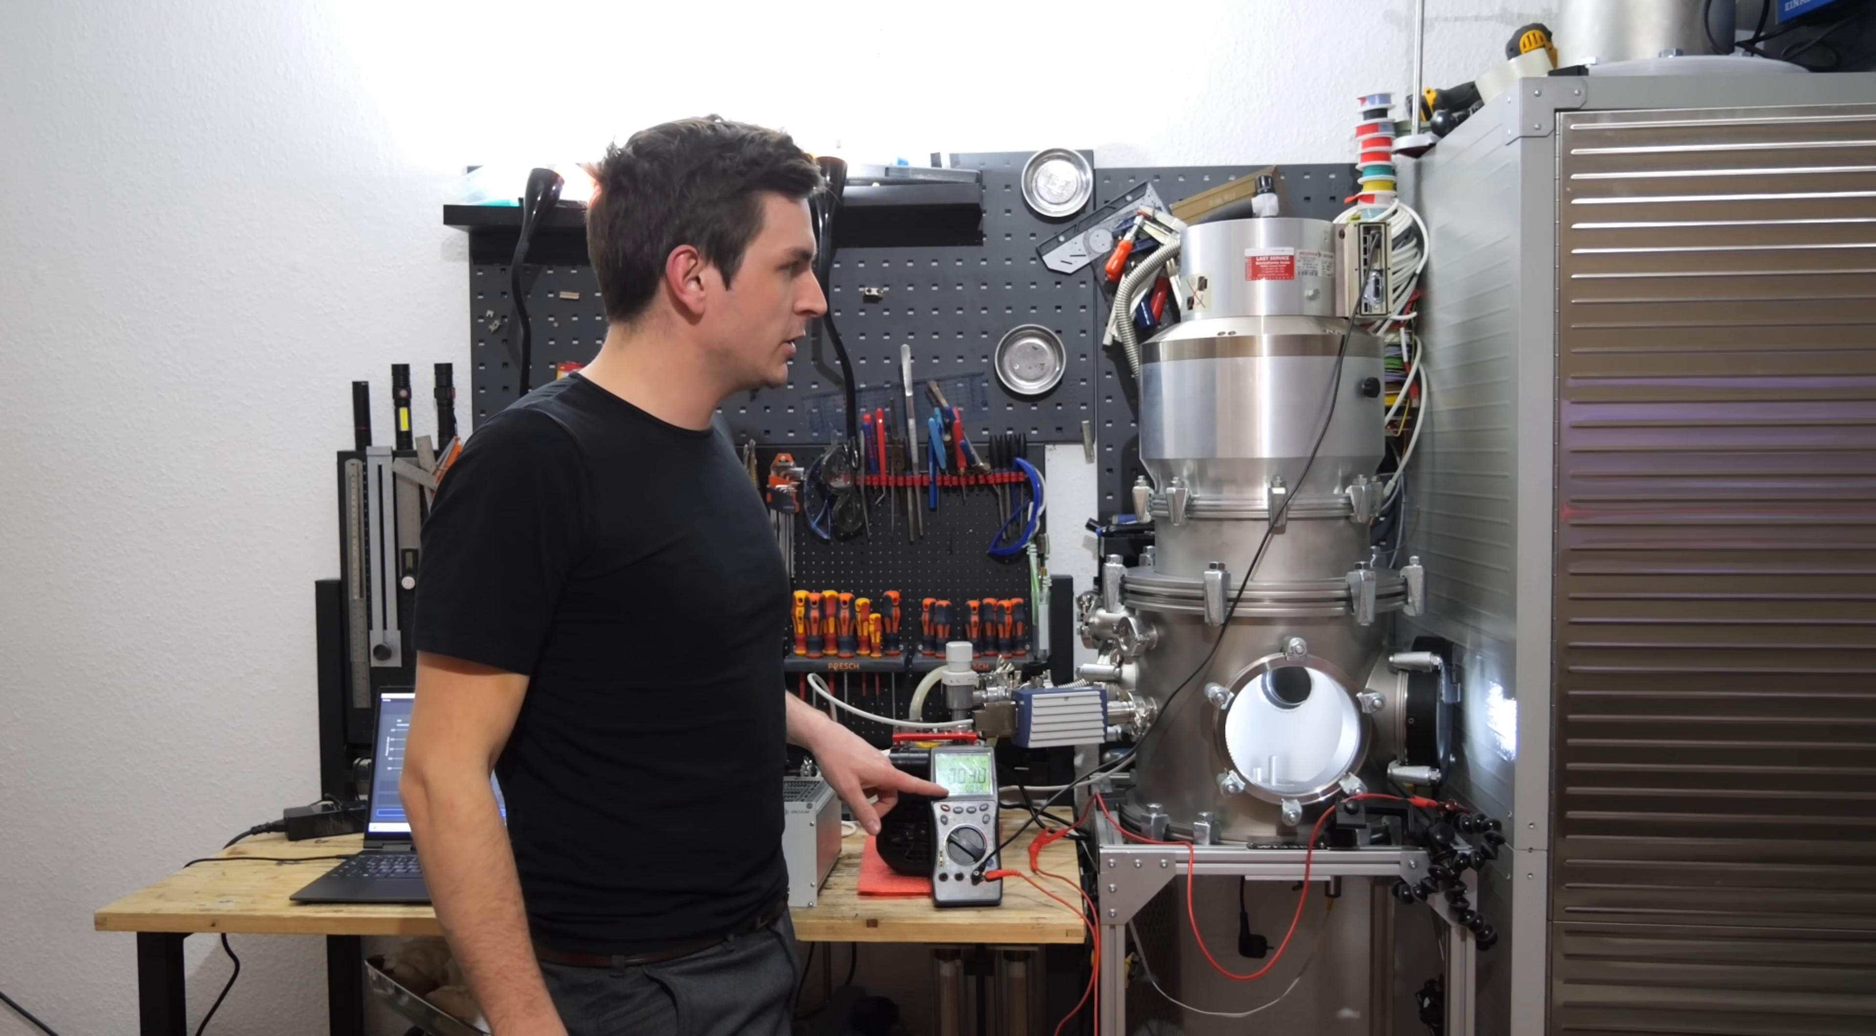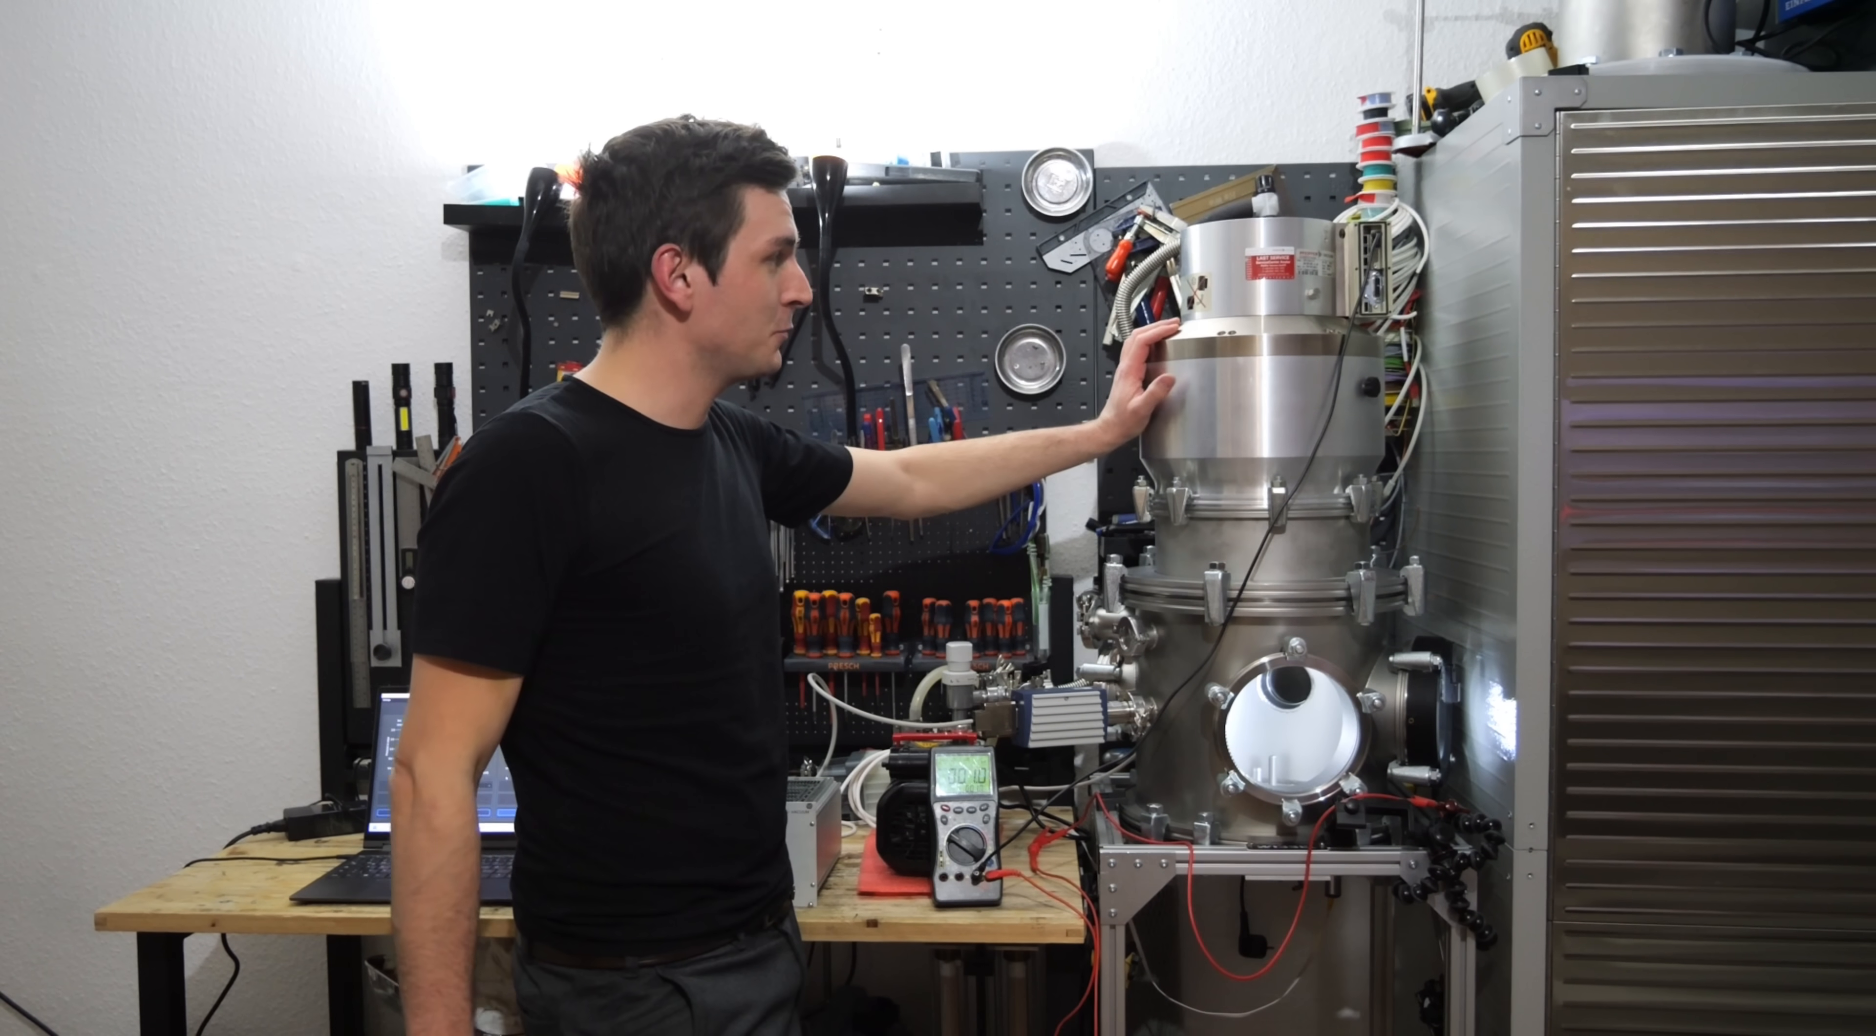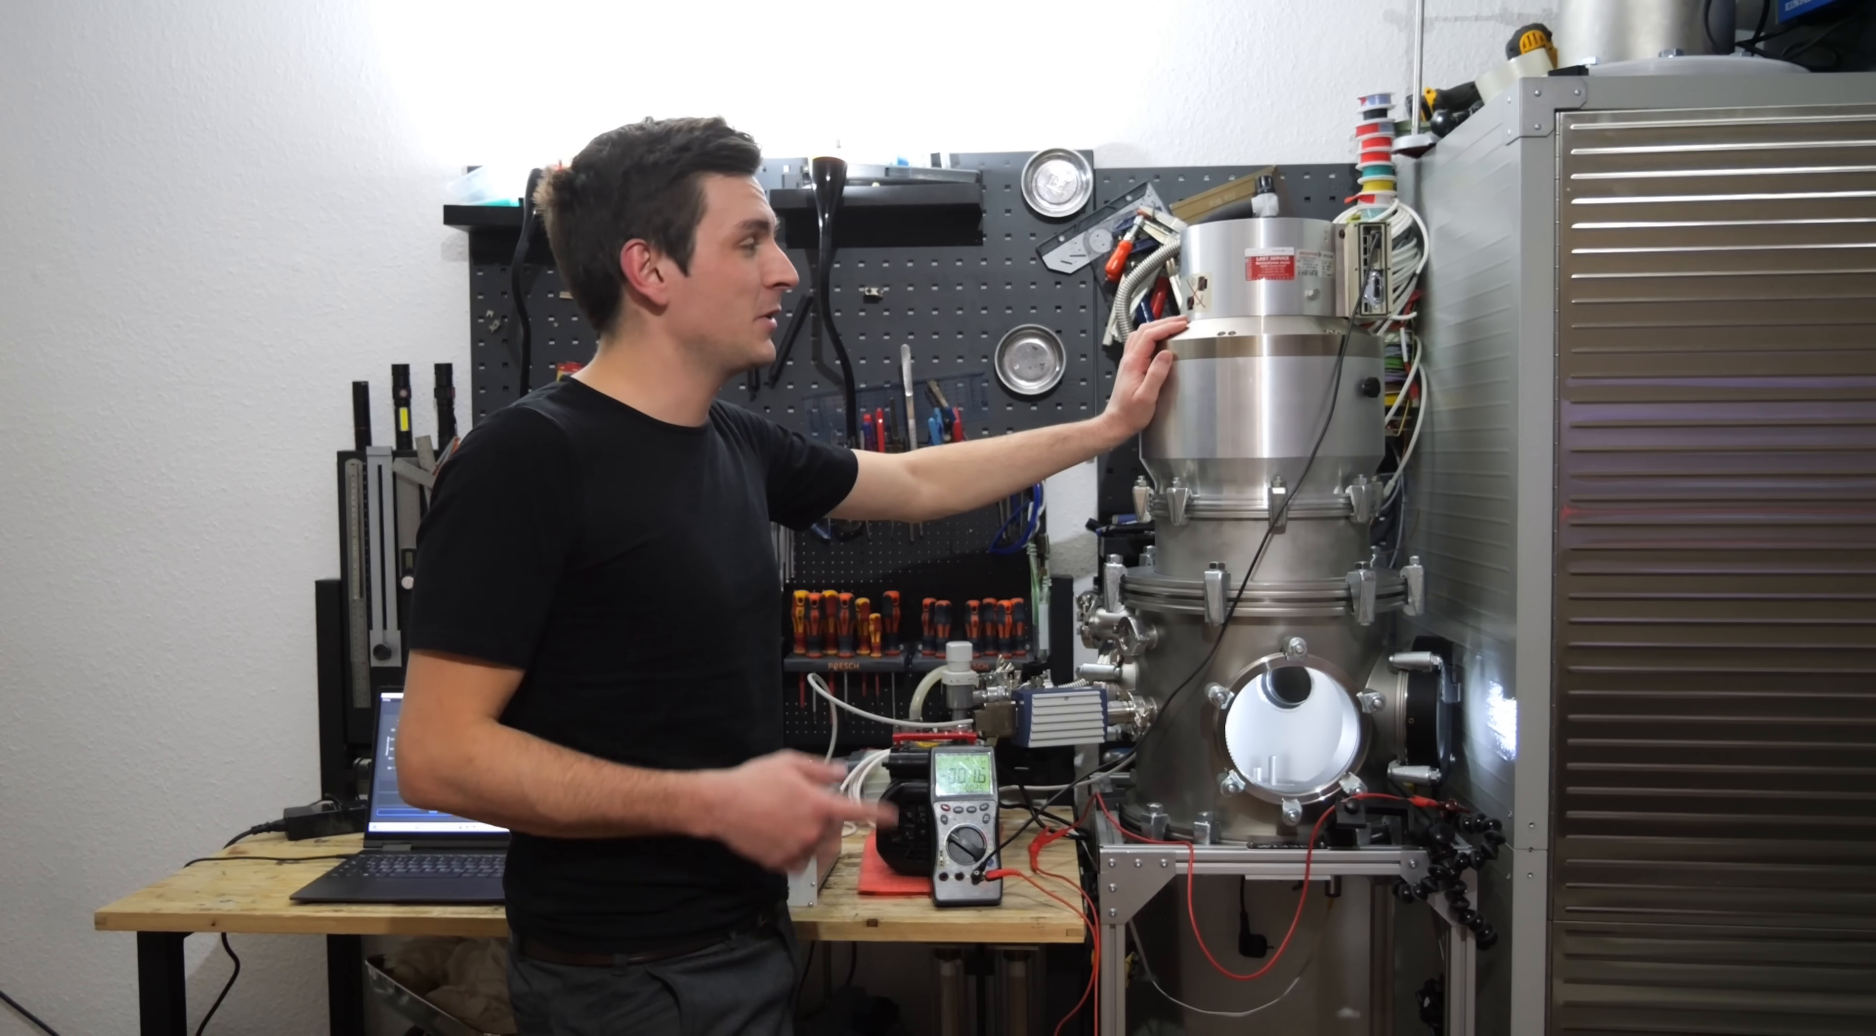At around 10% its maximum speed—I monitored the speed using my multimeter, it has an analog 0 to 10 volt output—you heard it. The pump makes noises you don't want to hear. So I'm not spinning this up any further.